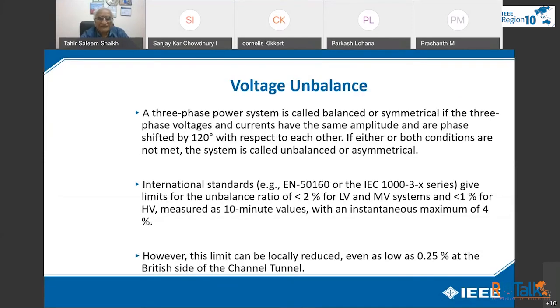A three-phase power system is called balanced or symmetrical if the three-phase voltages and currents have the same amplitude and are phase shifted by 120 degrees with respect to each other. If either or both conditions are not met, the system is called unbalanced or asymmetrical. International standards, for example European standard EN 50160 or the IEC 61000 series, give limits for the unbalance ratio of less than 2% for LV and medium voltage systems and less than 1% for HV, measured as a 10 minute value with an instantaneous maximum of 4%. However, this limit can be locally reduced, even as low as 0.25% at the British side of the Channel Tunnel.